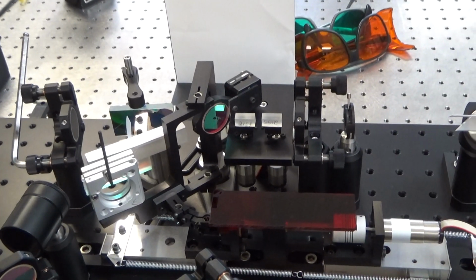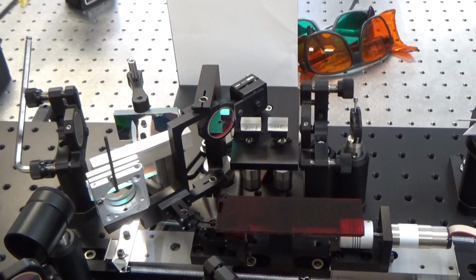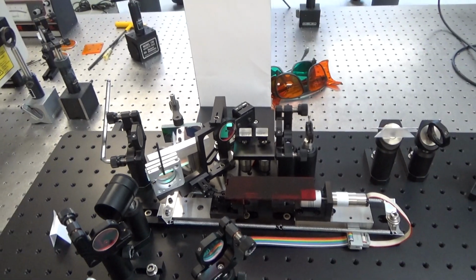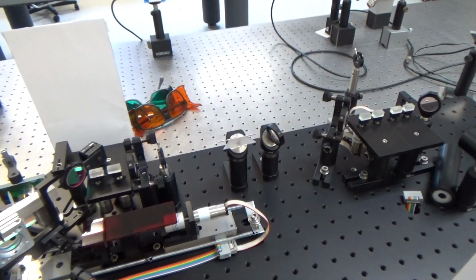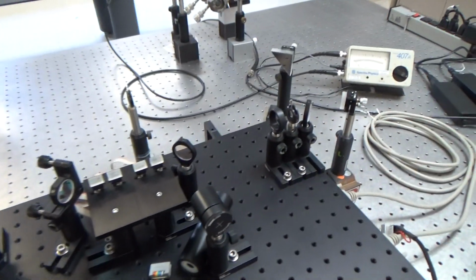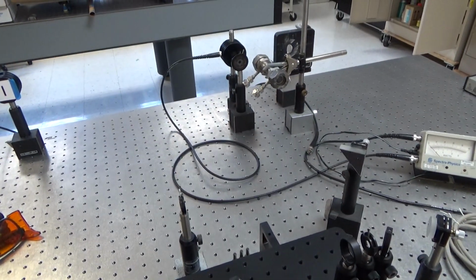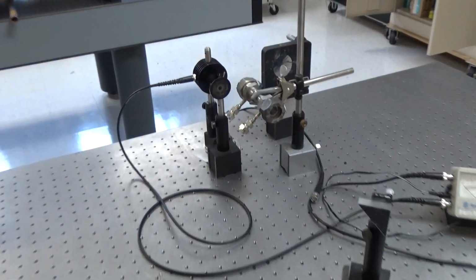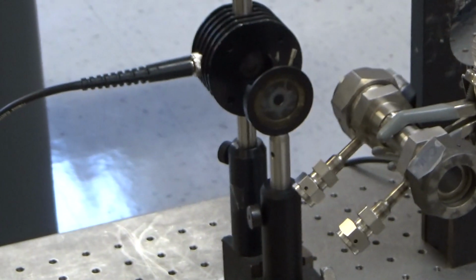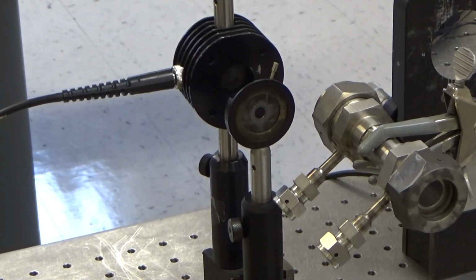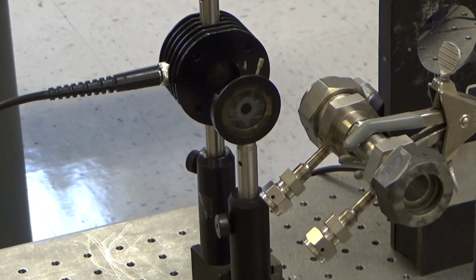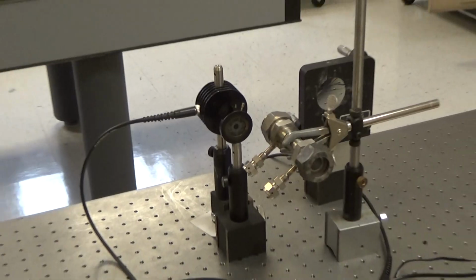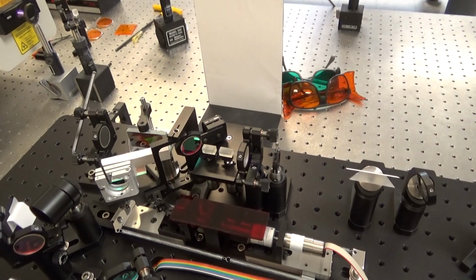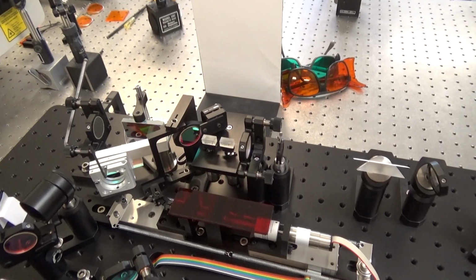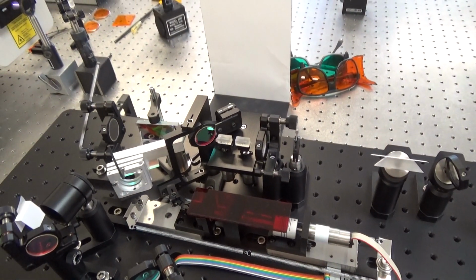When optimizing the system, I found that you get a much better calibration if you place your power meter not right after the OPO or at the output port, but about 50 centimeters from the output port, centered behind an aperture, about a 7 or 8 millimeter aperture that's centered on the green leakage from the OPO. That is the best position to actually do the calibration for these systems.